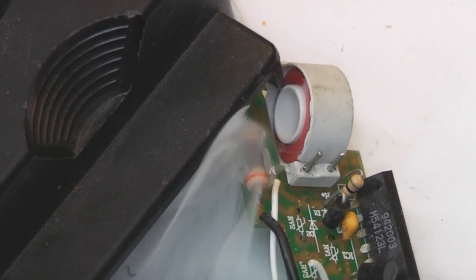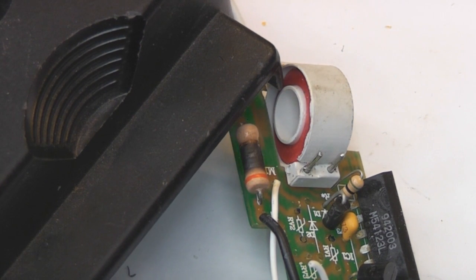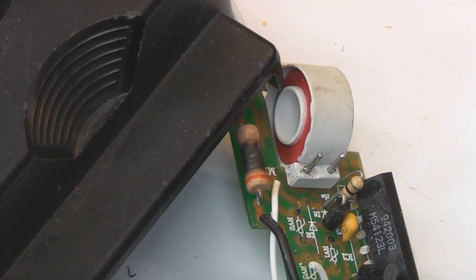Yes, it doesn't last very long, but I'm still a little bit surprised that it got hot enough to show burn marks just from the occasional test button operations. But then again, this breaker was faulty, it wouldn't trip, so that would explain it, because normally you'd press the test button, it would trip instantly, so you'd get hardly any power dissipation in that resistor. But because this breaker wasn't tripping, you'd hold the test button and it would put power through that resistor for as long as you held the button. So that explains exactly why that resistor was burnt, purely because the thing wasn't tripping.